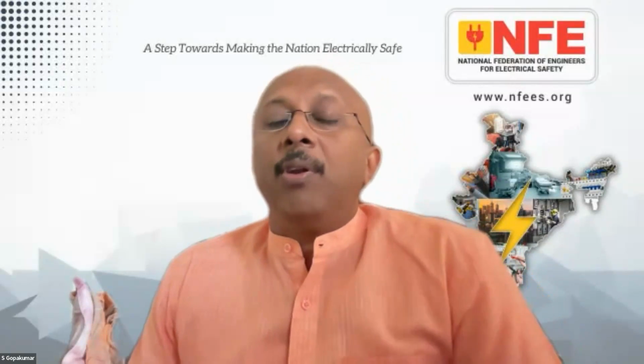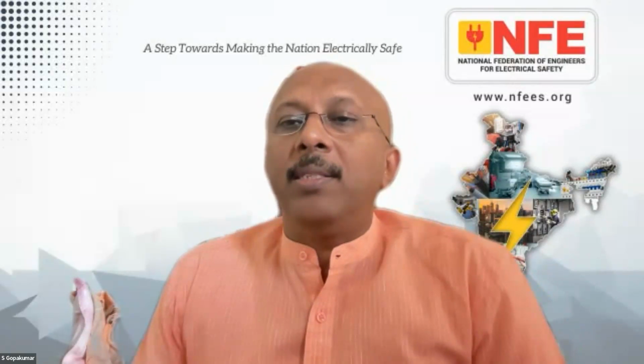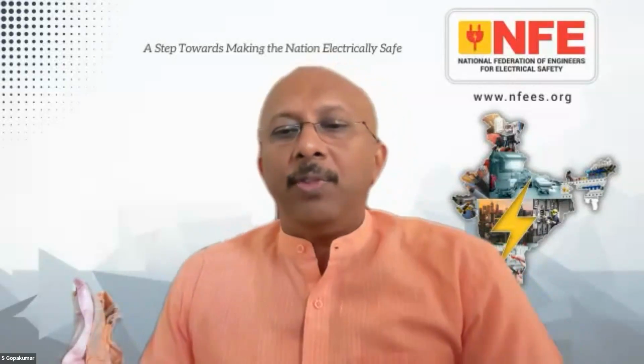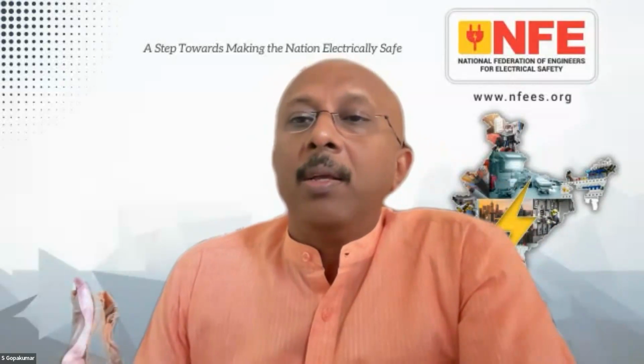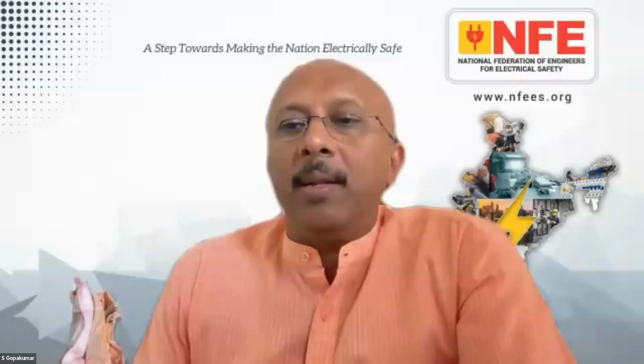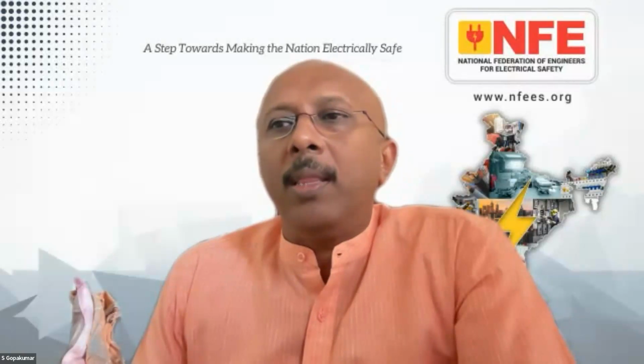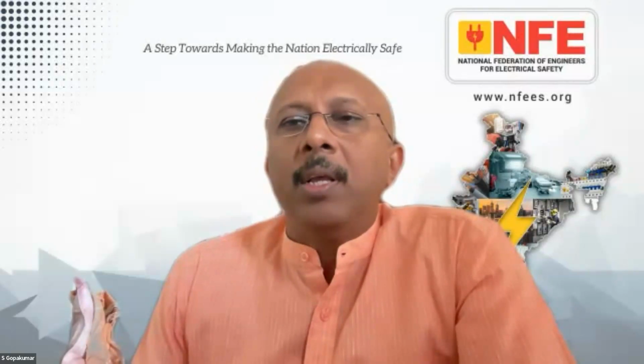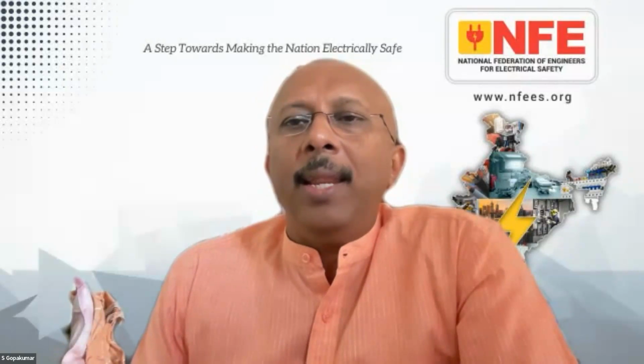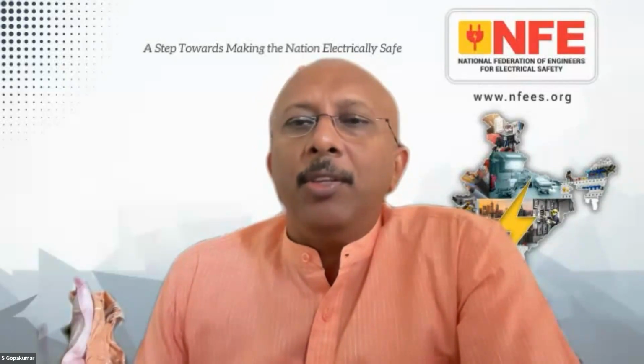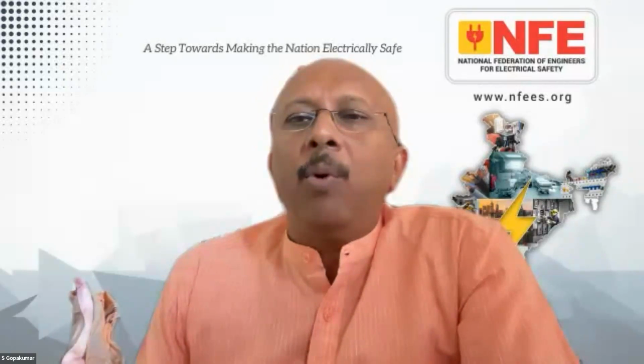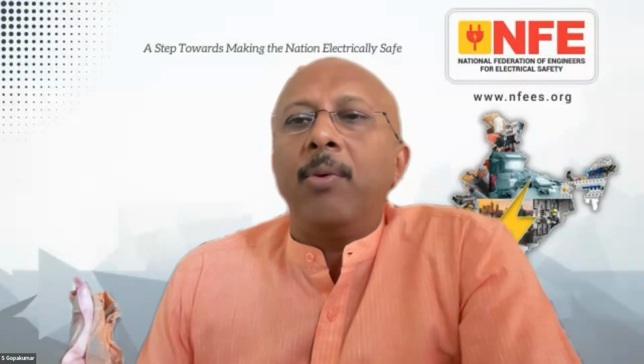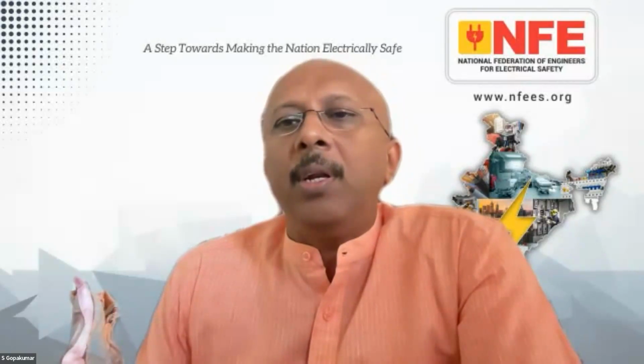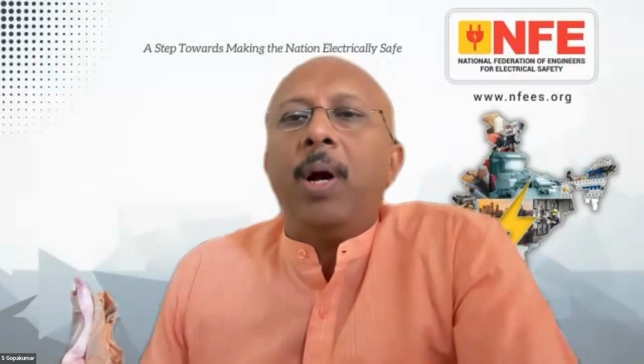Okay, is there any IS standard for neutral to earth voltage? As I said, there is no IS standard. There are different ways of checking it. For example, let's say you have a neutral conductor, a voltage between neutral and earth at the final distribution board means the voltage drop at the neutral conductor is equivalent to that particular voltage. Let's say, for example, 10 volt between neutral and earth. That means the voltage drop at the neutral conductor is 10 volt. This also means the line voltage also will have 10 volt drop. So at the consumer premise for the final circuit from the source, 20 volt is the drop.